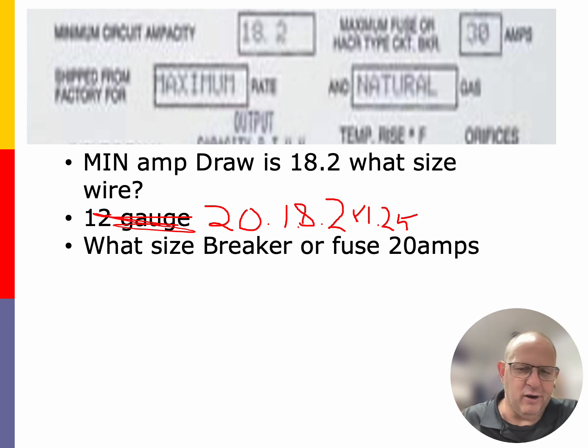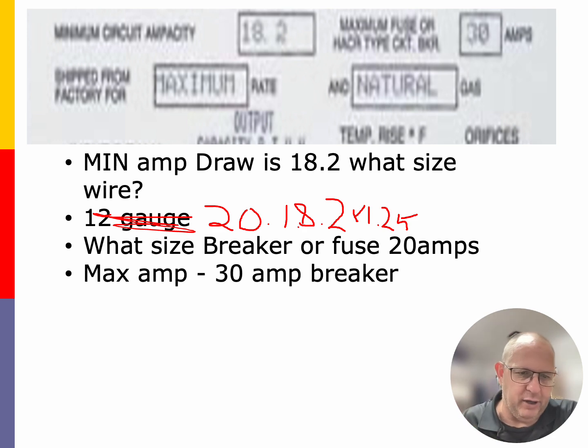So what size breaker? If I was to use a 20 amp, I would put in a 20 amp breaker or fuse if I was going to run 18.2. But we've already talked about that, and we've already discussed that we're going to be pulling over 20 amps on that particular unit. Now, the maximum amps for this one is a 30 amp breaker.